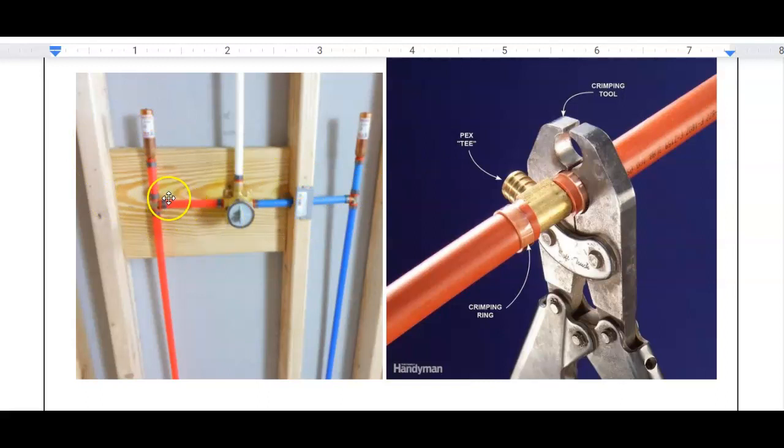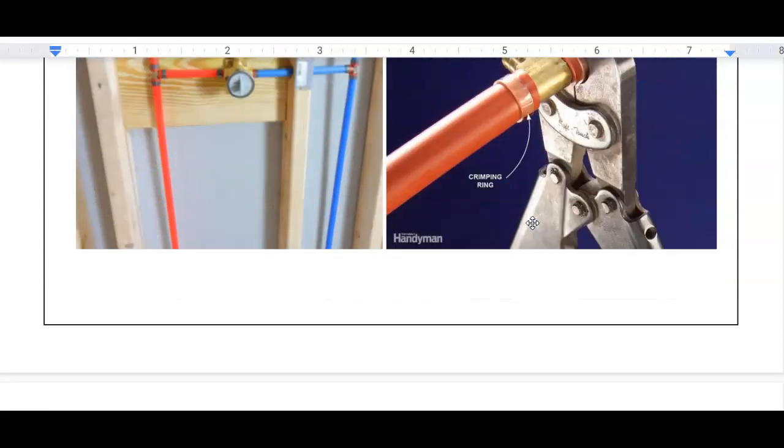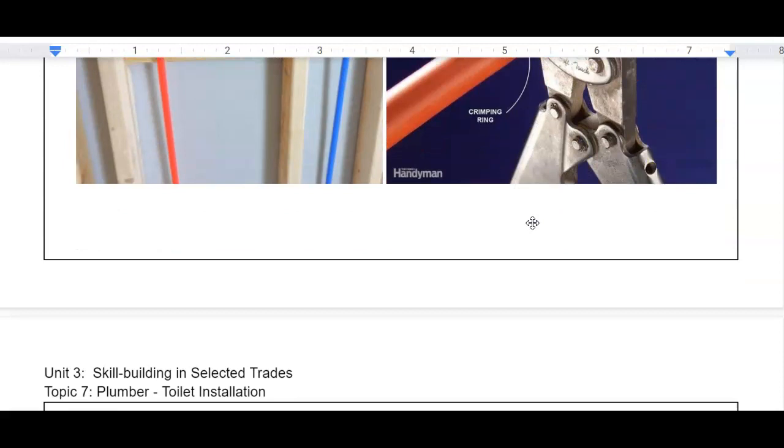So this is all the PEX, and it's joined with copper rings. You see an example of that here. It's called crimp rings. The different joints within that, here we call it a T, where you make a branch coming off of it. You put the PEX pipe on, slide the copper ring into its correct position, and then use the tool to tighten the copper ring down to give you a waterproof, permanent seal. And we'll go through that one right in the shop.